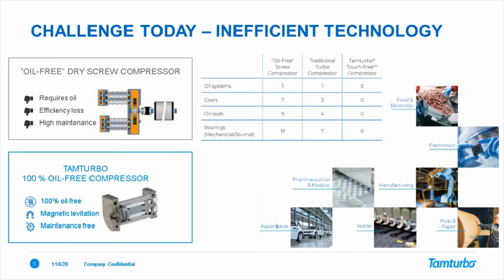And traditionally, this oil-free compressed air need has been met with the so-called oil-free dry screw compressor, and I have oil-free in quotation marks, because the compressor is really not oil-free. The yellow part, which you see in the picture on the top left, is actually the gearboxes and the oils. And when the unit operates, oil vapor exits the compressor, and then if you suck the air for the compressor from the compressor room, then you have oil vapor in the air, and then you will have oil in the resulting compressed air. The other risk, which actually happens surprisingly often, is that the only thing separating that yellow oil from the gray screws, which are actually doing the compression by rotating, is a shaft seal. So if that shaft seal leaks, you get the oil in the screws, and then you get the oil in the compressed air system, in the pipes, in the filters, in the dryers, and so on.